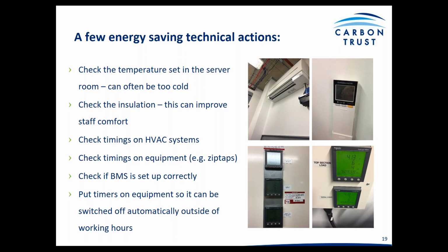Check if your building management system, or BMS, is set up correctly. Any system linked to the BMS typically represents 40% of a building's energy usage, and if lighting is included in this setup, then it can reach up to 70%. So please make sure that if you have a BMS, it's programmed and commissioned correctly.